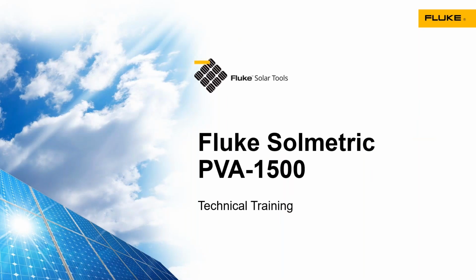And then I have the open and map functions, which allow me to find circuits that have a break in them, and find where the break in the circuit actually is. And then the map function, which allows me to identify circuits within a system where I have inadequate documentation. And this is really allowing technicians to locate and fix ground faults much faster than techniques that we've had previously. So now let's talk about the PVA 1500 IV curve tracer.